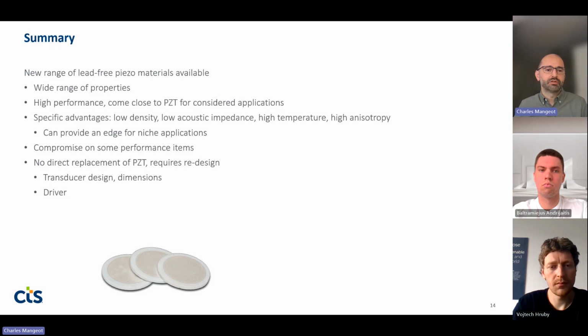However, in many cases, there will be some compromise. It is not a one-to-one replacement. And as both Vojtech and Baltra mentioned, there is some level of redesign that is required. So basically, you can achieve the same performance, but with a trade-off on some other properties. It may be at the transducer level, changing the dimensions to reach the same performance, adjusting the weight repartition to maintain the position of the nodal points, and so on.